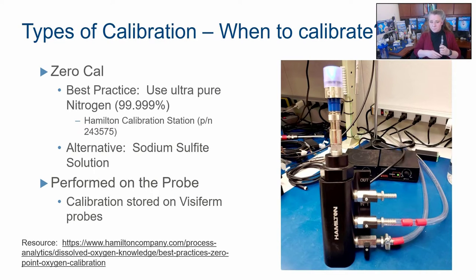Zero calibration. How do we do a zero cal? And this addresses your question, Ava. A zero calibration means zero oxygen. So how do you do that? There are two ways. Both are completely valid. And this is on the probe itself. It depends on your atmosphere. What you can see in the diagram there is a probe calibration station we have that works on our 225 millimeter length sensors only. I have sort of a version of it here.